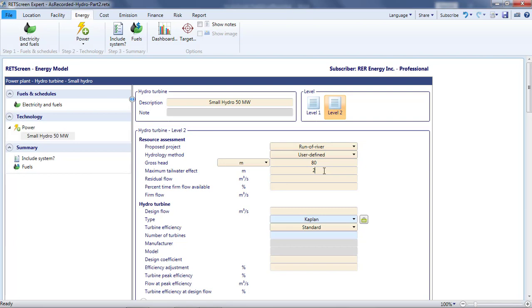The flow duration curve will dictate the flow in the water course. For environmental reasons, the project may need to leave some flow in the water course at all times. This is the residual flow. I don't know what the requirement would be for this site, but I'm going to set it to 10 cubic meters per second for this example. This is the minimum flow that occurs in the water course right now, and just under 15% of the mean flow. For a real project, I'd have to investigate.